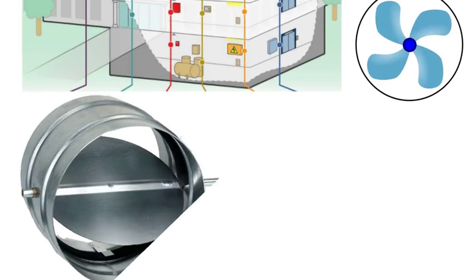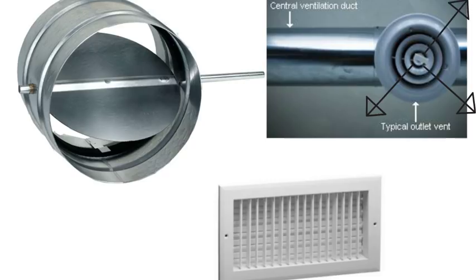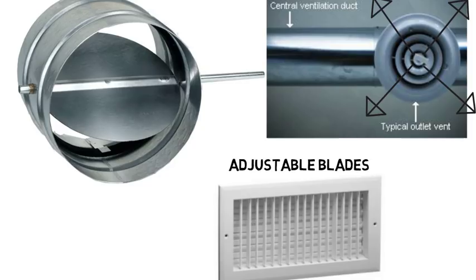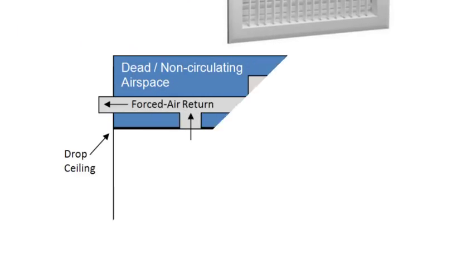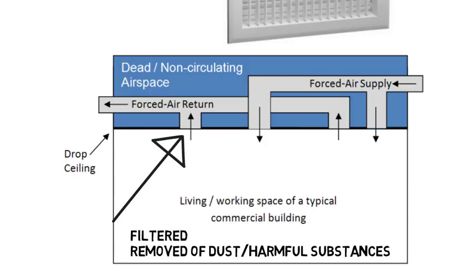What you can do is use different dampers that control how much air gets into certain parts of the building by closing a flap a certain amount, which can be automated or manual. The air that gets through can enter rooms through different devices like a register or diffuser. Air that exits a diffuser is distributed evenly, allowing for slower velocity air and raised static pressure. A register has adjustable blades that can control how much air gets through. You also have to consider where the air goes once it enters the room, and it has to leave back through the ducts and circulate throughout the building. The constantly circulating air needs to be filtered to remove dust or harmful substances — this is the ventilation part of HVAC. Some air also needs to be exhausted to the outside and replaced with fresh air to keep everyone safe and comfortable.